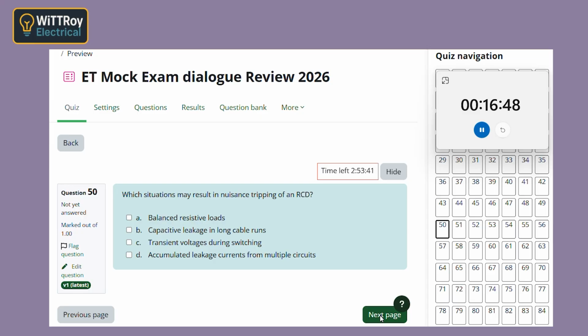Question 50. Which situations may result in nuisance tripping of an RCD? Leakage currents from lots of circuits, I think? Yes, let's go deeper. A single device may only leak a tiny amount of current to earth, not enough to trip an RCD. But if several devices are on the same RCD, those little leakage currents can add together. So even though nothing is badly faulty, the total leakage may still reach the trip point. Exactly. That's one common reason.